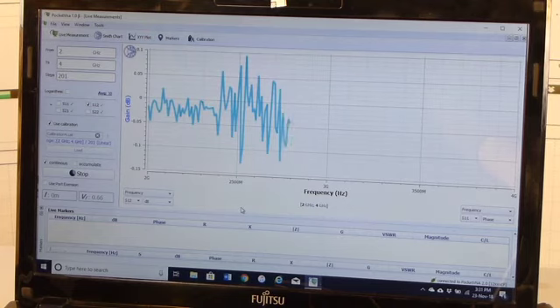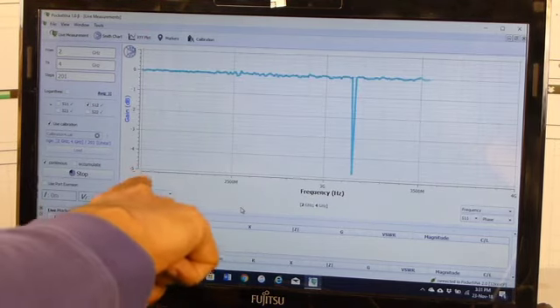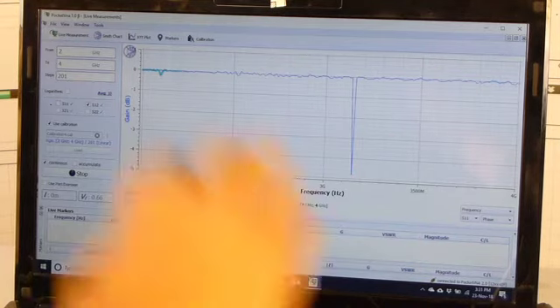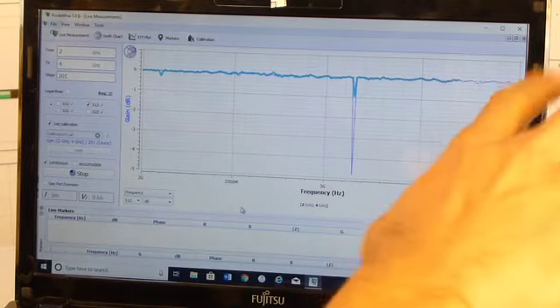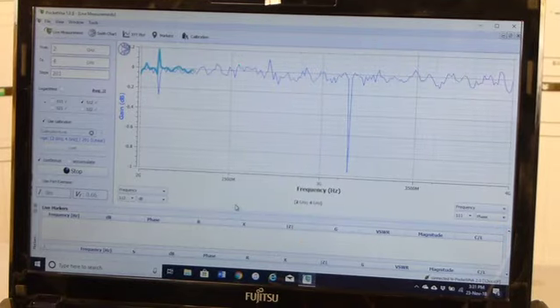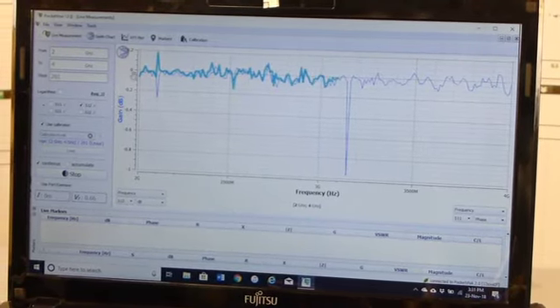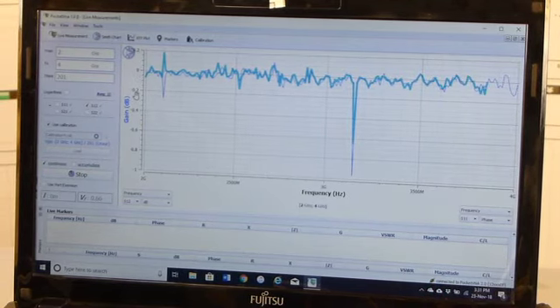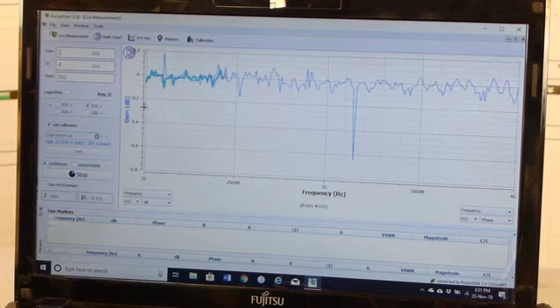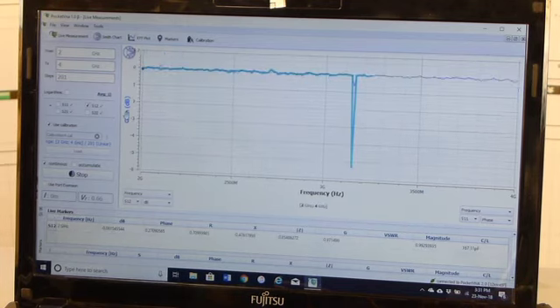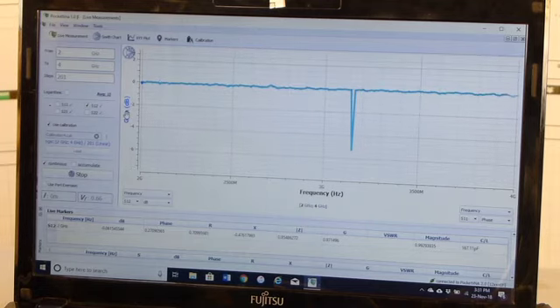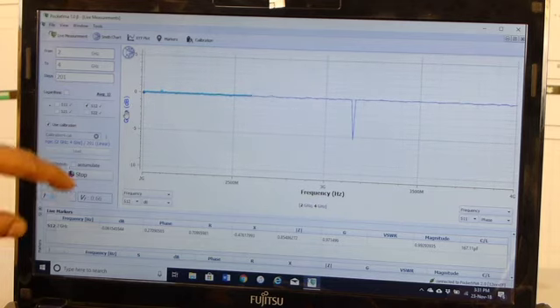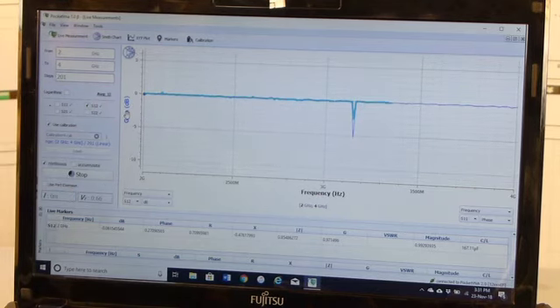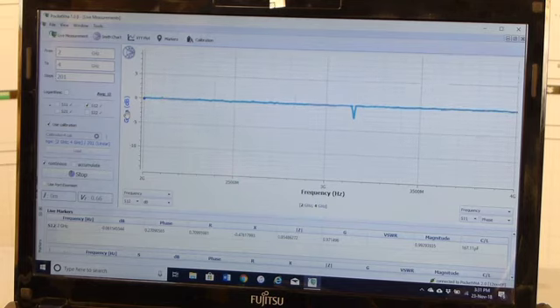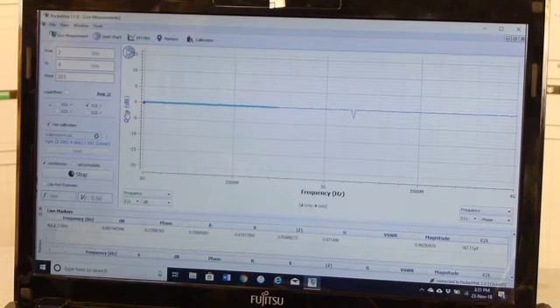Now as you can see, it is scanning from 2 gigahertz to 4 gigahertz and taking readings, which appear to have lots of standing wave or flatness issues. These issues are because the scale we are using is 0.2, which is a very, very fine scale. So we will use the cursor scroll feature and scroll it. As you can see, the scaling is changing, and now it is 0 to 10 dB. Again, now it says 0 to 20.